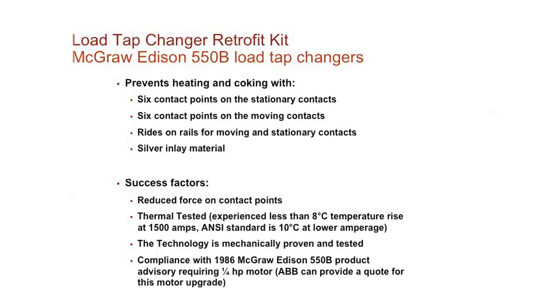Success factors: we have a reduced force on the contact, which means you have less contact wear. And then we've thermally tested it, mechanically proven them with over 1 million operations on a tap changer to prove that these contacts are doing exactly as designed, and then we can get many years of service out of them.